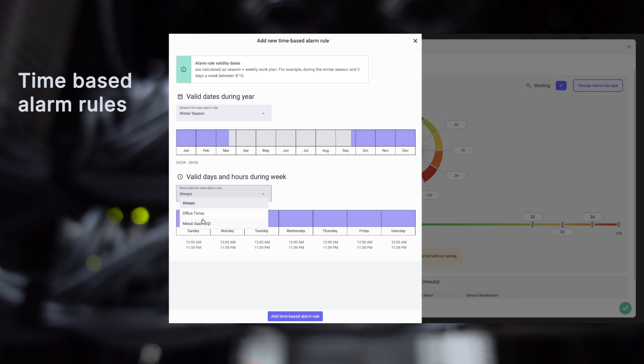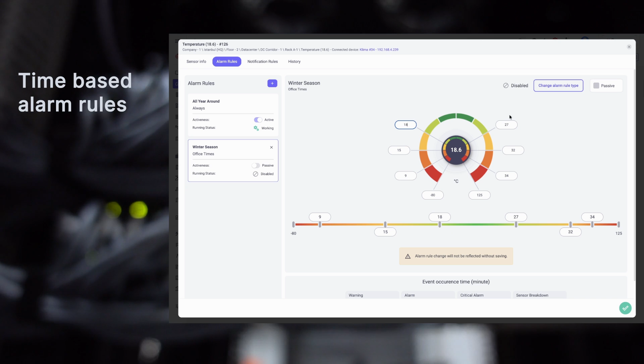But it may be concerning if it stays that high overnight when load should be lower. Precisely, or maybe thresholds need to change seasonally. 25 degrees might be a minor warning in summer, but a critical issue needing immediate attention in the dead of winter if the heating failed. So the system adapts its sensitivity to the operational context, whether that's time of day, shift patterns, or even the season.